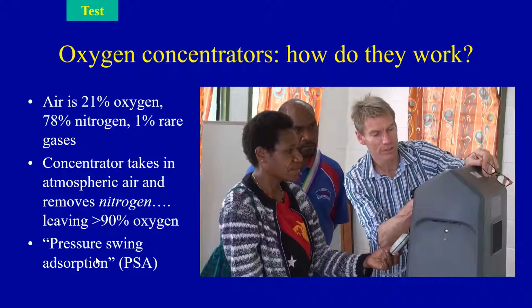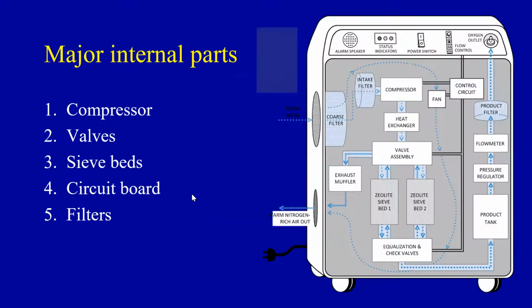I'll try to explain what that is. It's where the oxygen concentrator is moving between the cylinders inside the concentrator, pushing air into one of the cylinders to absorb the nitrogen and make oxygen. Then it moves to the other cylinder and removes the nitrogen to make oxygen, and then it moves back to the other one. I'll show you, I'll take the back off the concentrator and show you.